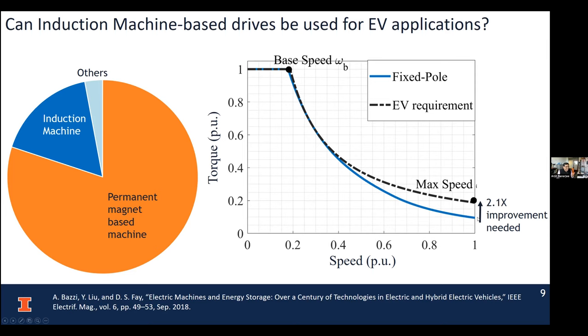At maximum speed, we will never be able to achieve the torque requirement. We need almost twice the improvement from the current state of the art to achieve the torque speed characteristic. So what's the way out? Either you over-design the machine or over-design the drive to reach this requirement at maximum speed. This is the classical divide and conquer approach, where we don't worry about power electronics and the machine and vice versa, and we run into a problem where we have to oversize the drive and machine to solve it.